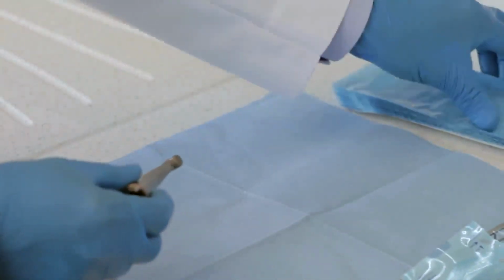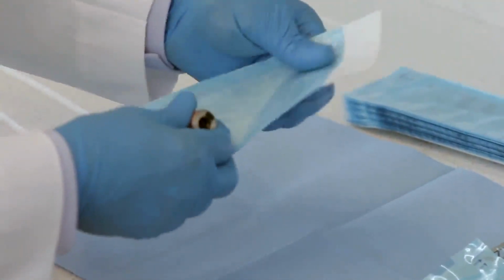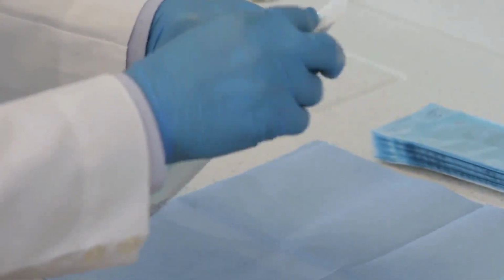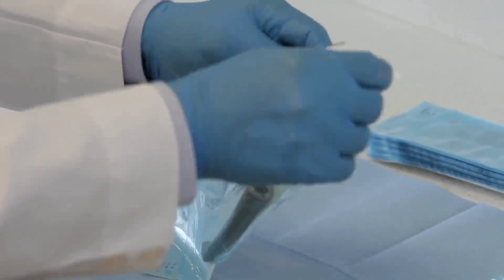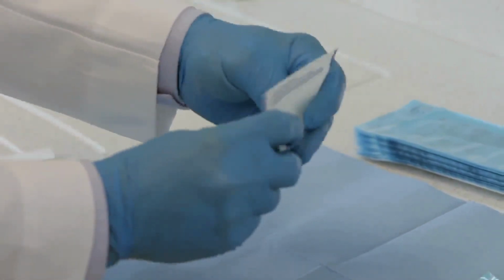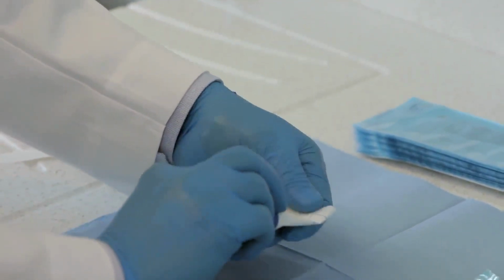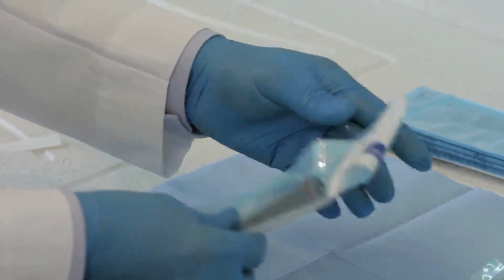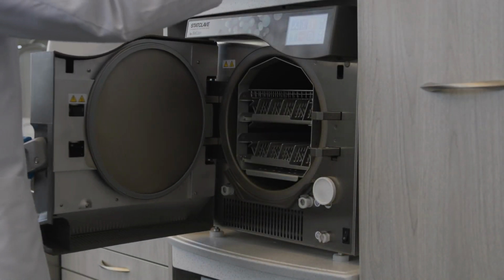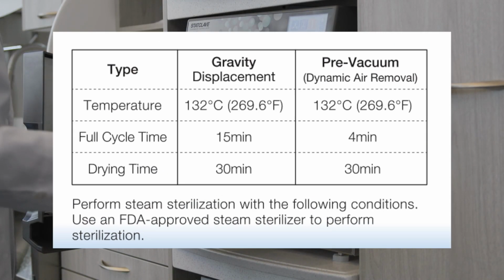Autoclave sterilization is recommended. Insert sterilizable components into a U.S. FDA-cleared sterilization pouch compliant to ISO 11607-1. Seal the pouch. Use this chart for temperature and timing.